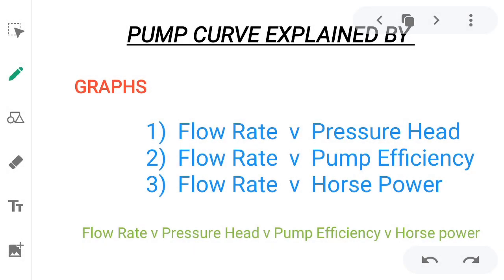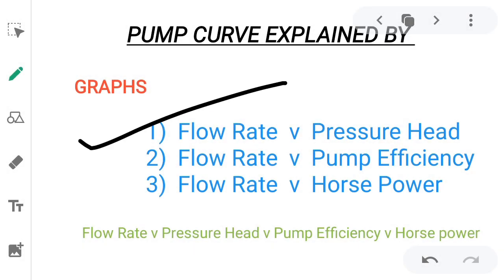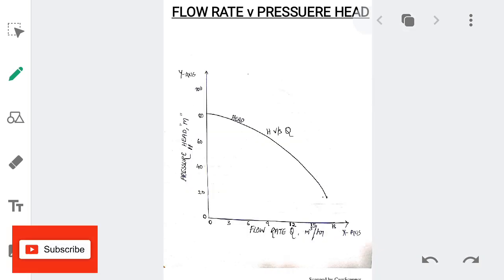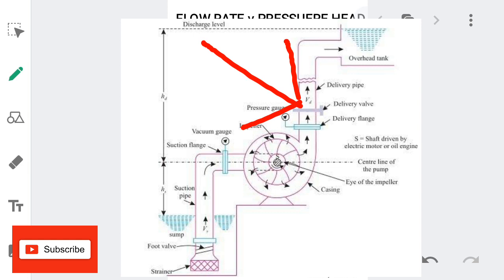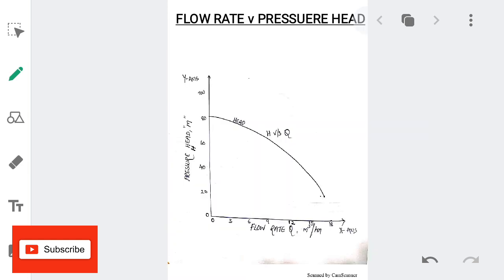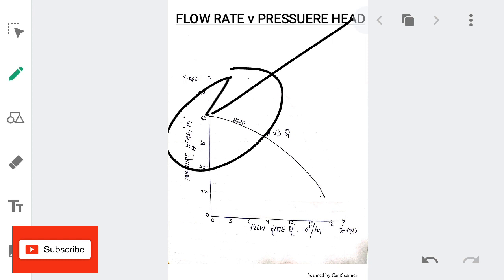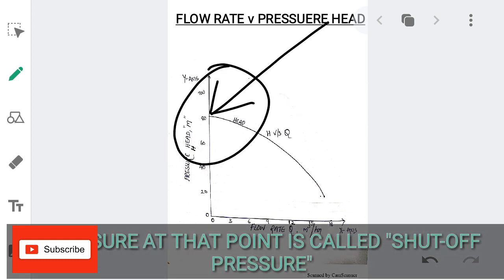The first module is flow rate versus pressure head. Flow rate is on the x-axis, represented by Q with unit cubic meters per hour, and pressure head is on the y-axis, represented by H with unit meters or feet. Consider a centrifugal pump running with the discharge valve closed — the pressure inside builds up and the pressure head at that point will be maximum. This is known as the shut-off point.